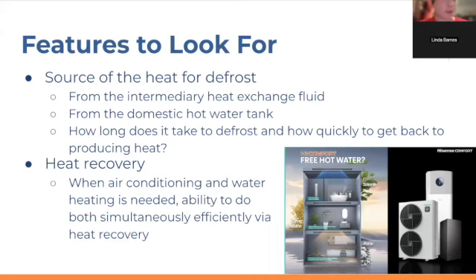Now, a feature to look for in combi heat pumps is how the combi heat pump system does defrost. It's a good question to ask because now you are combining domestic hot water heating and space conditioning together. So you don't need to use your space conditioning air handler to grab the heat for defrost anymore. You can grab it from the domestic hot water tank, and you'll cool down the water in your tank maybe 2 degrees, but is that noticeable? No. So you can get fast defrost without having a significant amount of time where you notice the defrost happening. So that's really cool.